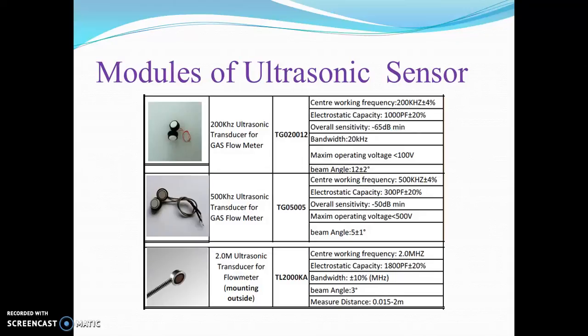This picture shows models of ultrasonic sensors with their specifications. First one is a 200 kHz ultrasonic transducer used for gas flow meters, with the model name TG020012. Its center working frequency is 200 kHz with tolerance 4%. Electrostatic capacity is 1000 picofarad with tolerance 20%. Its bandwidth is 20 kHz. Its maximum operating voltage is less than 100 volt. The second one is a 500 kHz ultrasonic transducer for gas flow meters. And the third one is an ultrasonic transducer for flow meters. Its working frequency is up to 2 MHz.